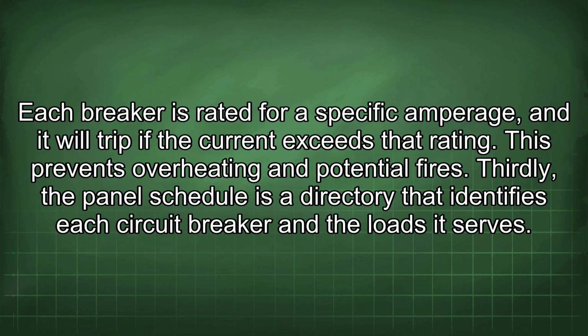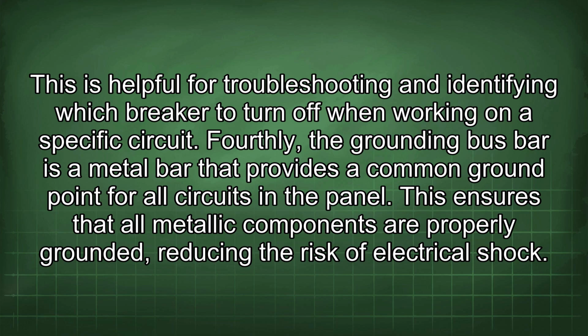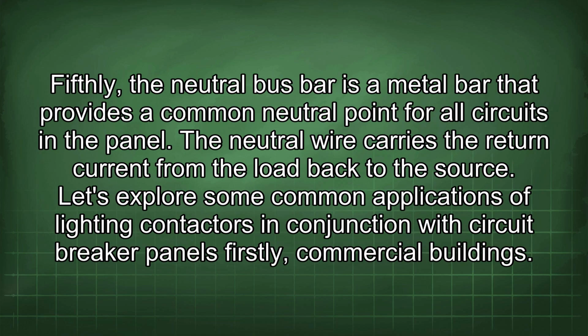This prevents overheating and potential fires. Thirdly, the panel schedule is a directory that identifies each circuit breaker and the loads it serves. This is helpful for troubleshooting and identifying which breaker to turn off when working on a specific circuit. Fourthly, the grounding bus bar is a metal bar that provides a common ground point for all circuits in the panel. This ensures that all metallic components are properly grounded, reducing the risk of electrical shock. Fifthly, the neutral bus bar is a metal bar that provides a common neutral point for all circuits in the panel. The neutral wire carries the return current from the load back to the source.